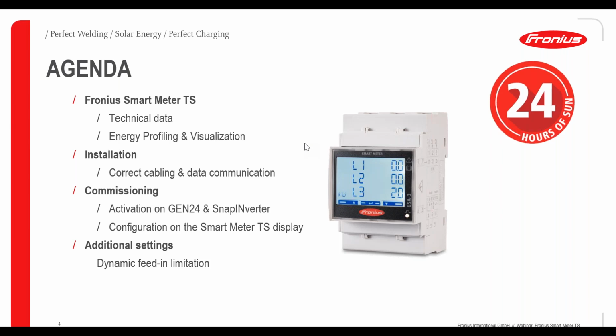Then we continue with the installation of the smart meters, the correct cabling of the smart meters to the data communication card of the inverter. Then after the installation, we need to do the commissioning of the smart meter, of course, either on our old Snap inverter models or our Gen 24 hybrid inverters.